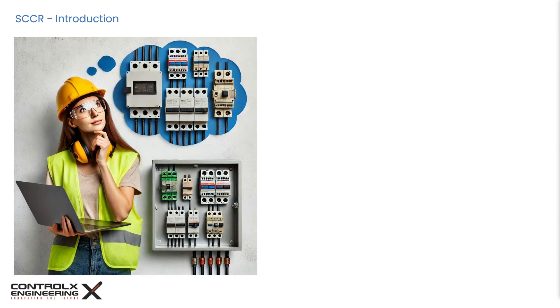Let's start with the basics. SCCR stands for short circuit current rating, and it represents the maximum current a component or equipment can safely withstand without causing damage or a safety hazard during a short circuit event. In simple terms, it tells you how much current the equipment can handle if something goes wrong. Exceeding this limit could result in fires, explosions, or projectile hazards — making it a critical specification in industrial electrical systems where large amounts of power are involved.